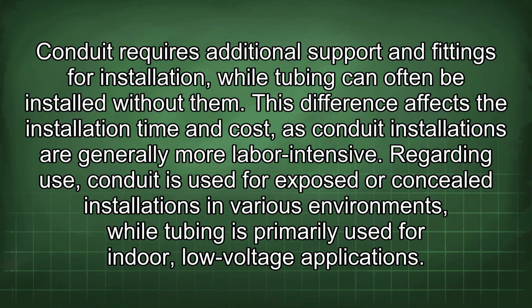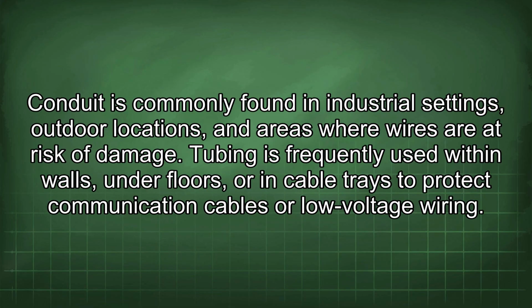Regarding use, conduit is used for exposed or concealed installations in various environments, while tubing is primarily used for indoor, low-voltage applications. Conduit is commonly found in industrial settings, outdoor locations, and areas where wires are at risk of damage. Tubing is frequently used within walls, under floors, or in cable trays to protect communication cables or low-voltage wiring.